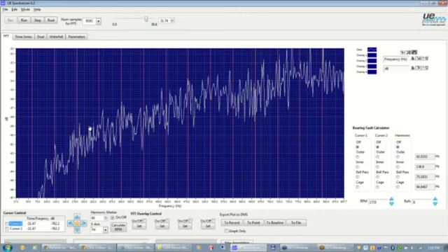The frequency noise that's occurring within there is related to where the discharges of energy, depending on if it's tracking or arcing, are taking place and occurring relative to the electrical sine wave on a 16 millisecond time base. In other words, one electrical cycle is a time base of 16 milliseconds. A discharge of energy can occur at any point or multiple points within that 16 milliseconds, and that is one of the contributing factors to this activity that we see in between each 60 hertz harmonic.